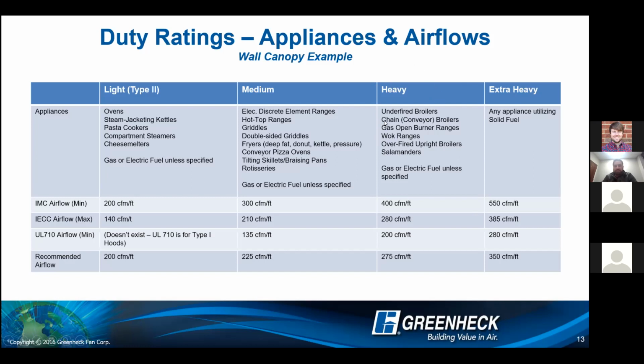Once we know that we have a heavy designation, and keeping in mind that when you're sizing these hoods, and we'll talk about overhangs a little bit later, the minimum overhang from the edge of the appliance needs to be a minimum of 6 inches. That's going to get us to the length of our hood. So once we've laid out that appliance lineup, determined the length of our hood, and determined that it's a heavy classification, next is, okay, what is our airflow? Now, IMC is going to call for minimum airflows of a heavy application of 400 CFM per foot. That's going to be out of IMC section 507.